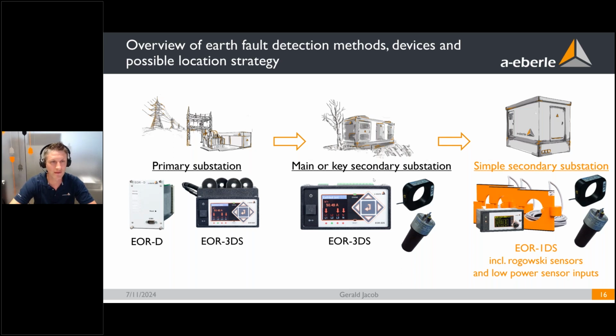On one hand, the primary substations, where a-eberle also comes from, out of primary substations with our regulators for transformers and arc suppression coils. Here we also have dedicated devices, the EOR3D, for earth fault detection, which only works together with CBCTs, but can overlook 4 feeders at the same time.